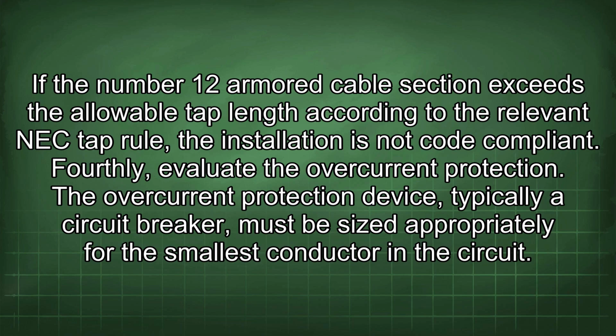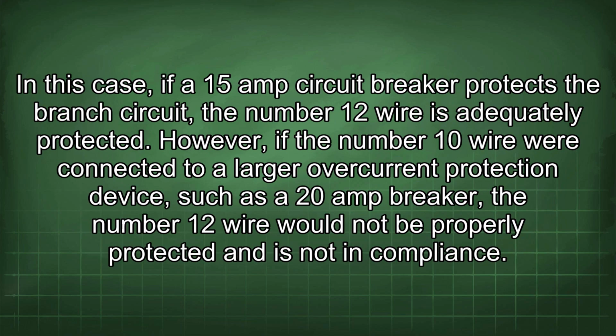Fourthly, evaluate the overcurrent protection. The overcurrent protection device, typically a circuit breaker, must be sized appropriately for the smallest conductor in the circuit. In this case, if a 15-amp circuit breaker protects the branch circuit, the number 12 wire is adequately protected. However, if the number 10 wire were connected to a larger overcurrent protection device, such as a 20-amp breaker, the number 12 wire would not be properly protected and is not in compliance.